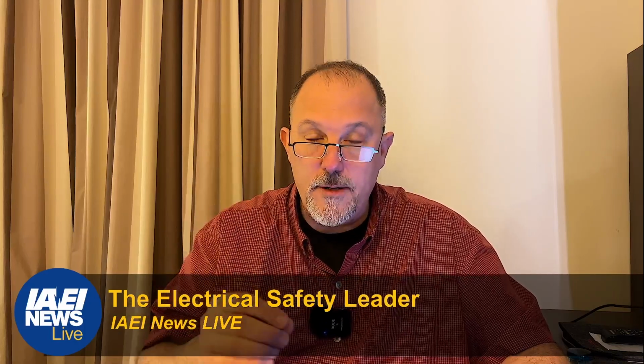So just to tell you how it's used, section 210.7. Go to your NFPA link and look that one up. 210.7 is multiple branch circuits. If two or more branch circuits supply devices or equipment on the same yoke, duplex receptacle, or mounting strap, a means to simultaneously disconnect the ungrounded supply conductors shall be provided at the point at which the branch circuits originate.